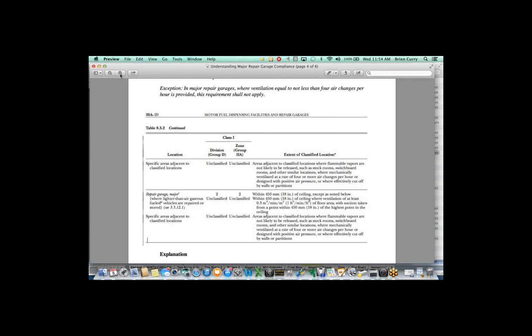So as we size these facilities up for maintenance for a CNG vehicle, we included fans that would be dispersed evenly amongst the ceiling, with their intake directly even with the highest point of the ceiling. We install a methane monitoring system tied to these fans, so that if there was a 25% LFL, it would immediately turn the fans on. It would either open up an overhead door to allow fresh air to come back in, which is perfectly legal, or we would tie in a fresh air intake with louvers somewhere on the lower half of the building, so that we're basically exhausting the air in the building via emergency ventilation if there was a 25% buildup or LFL. So they work very well. That's what I do in all of my shops now.